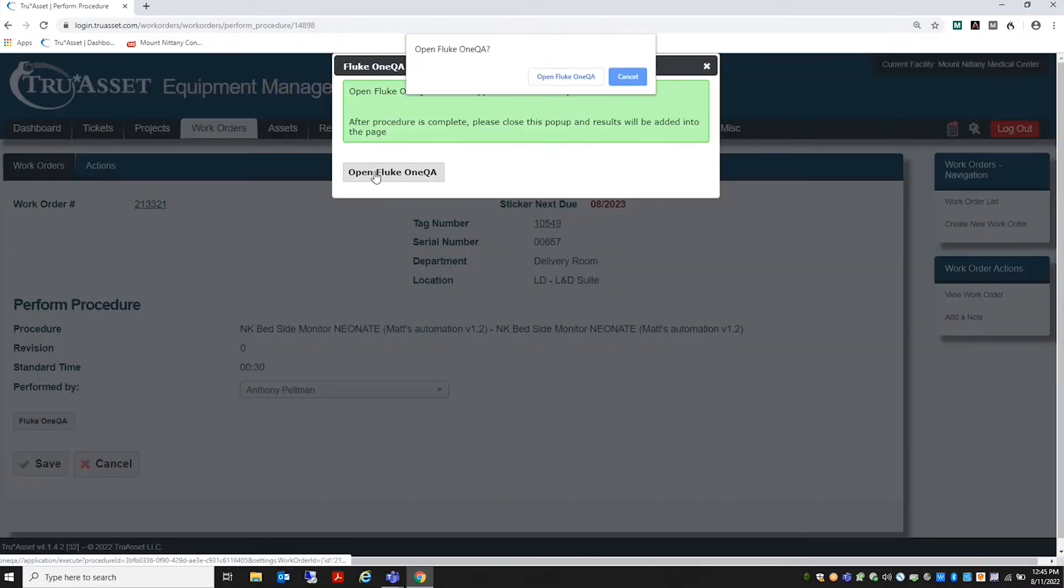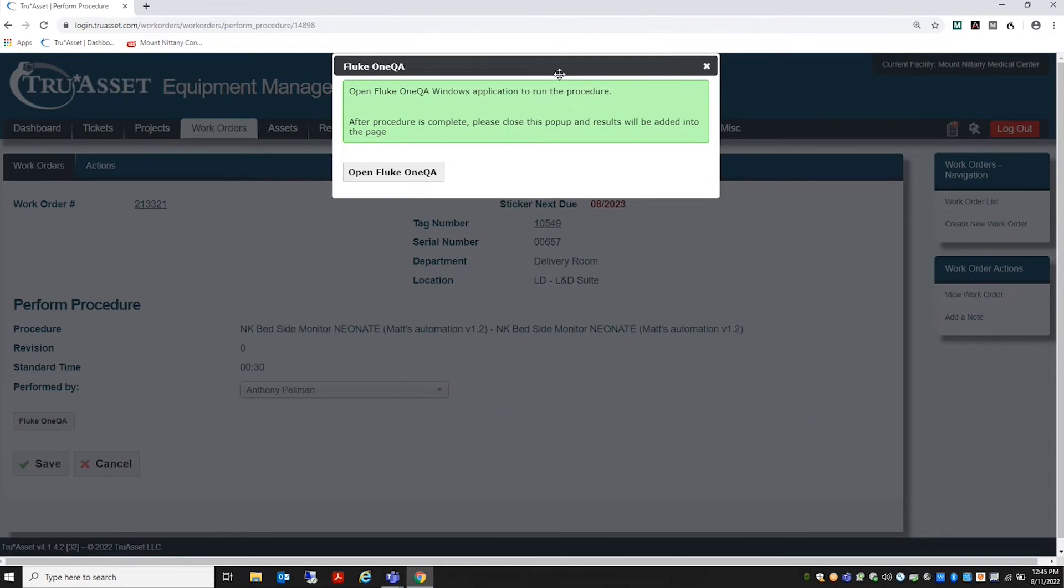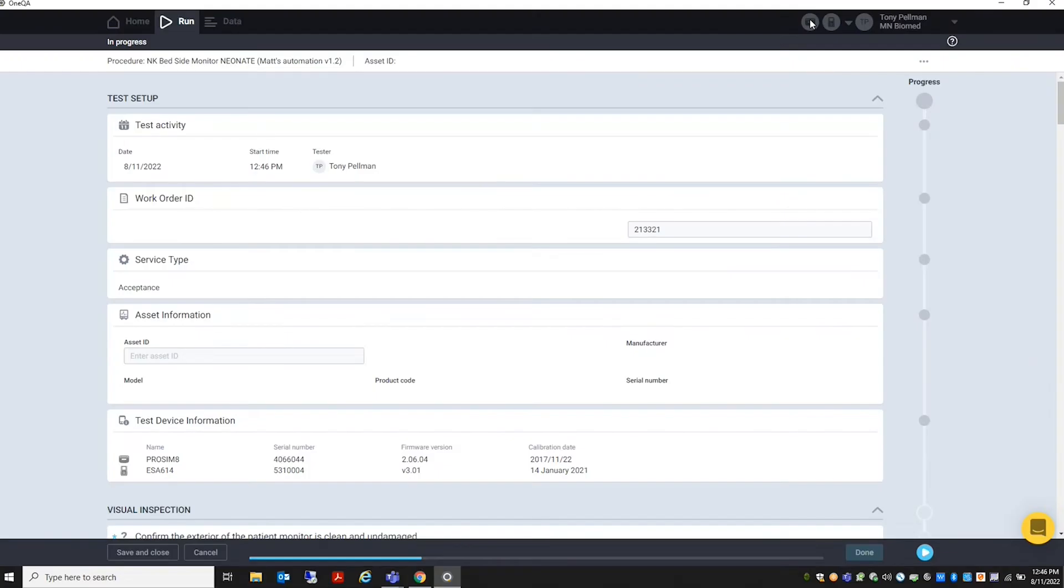OneQA will open and the DUT's information is already populated. You see that any interoperable Fluke test equipment's model, serial number, firmware version, and calibration date are already populated in the OneQA procedure.